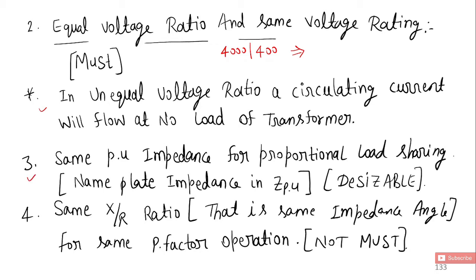Point number three: Same per unit impedance for proportional load sharing. In the upcoming lecture I will tell you about this proportional load sharing. Z per unit is written on the name plate of the transformer. This is not a required condition, this is desirable.